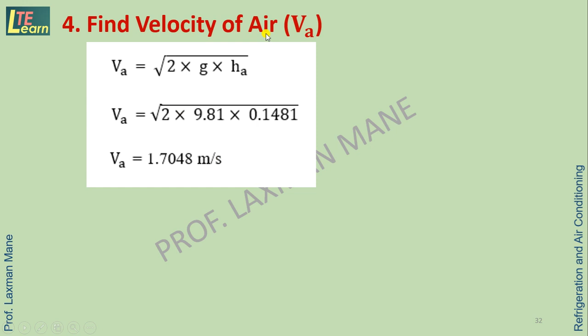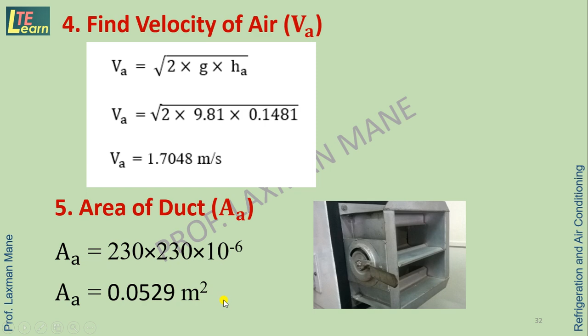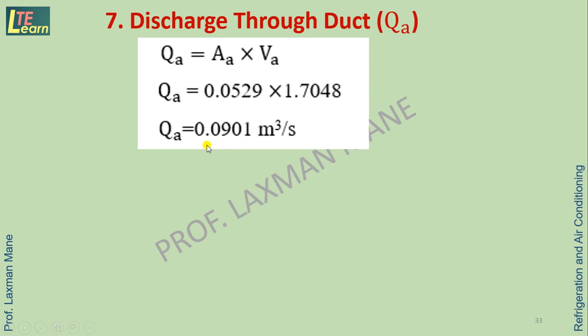Putting the value of HA here and calculating, we find the value in meter per second, that is the velocity of air. The shape of the duct is rectangular and dimensions are given in mm, so we convert the area of the duct into meter square. By calculation we find the area of the duct in meter square. Discharge of air passing through the duct is obtained by using the formula area into velocity of the air. So with area of the duct in meter square and velocity in meter per second, we find discharge in meter cube per second.